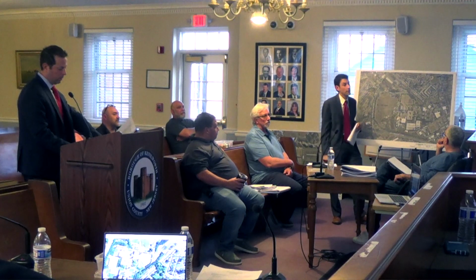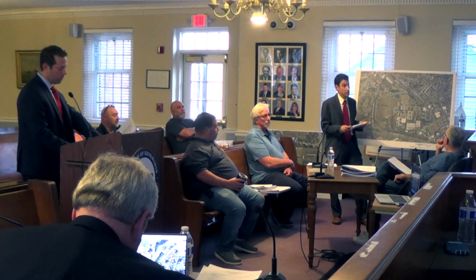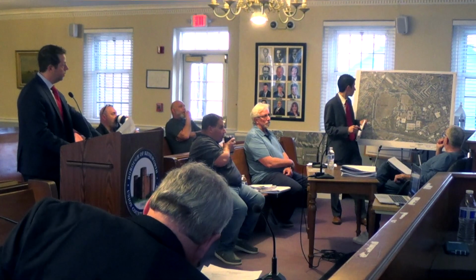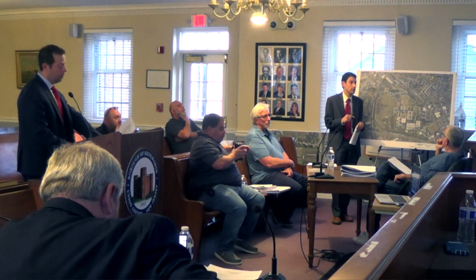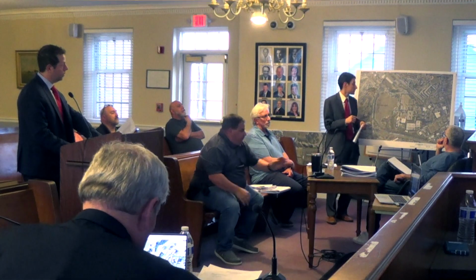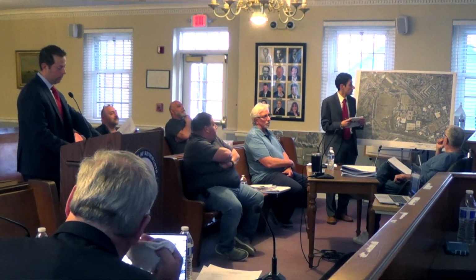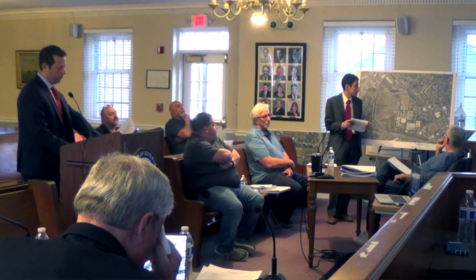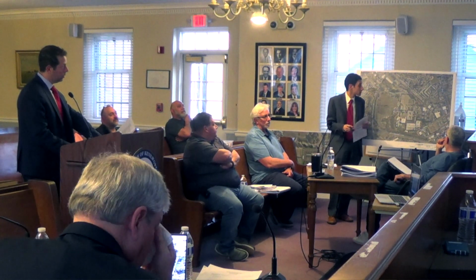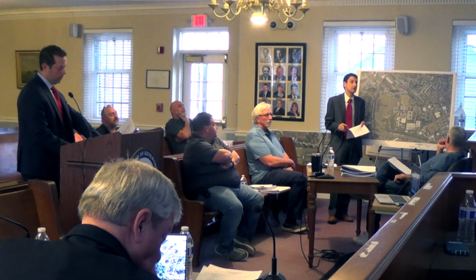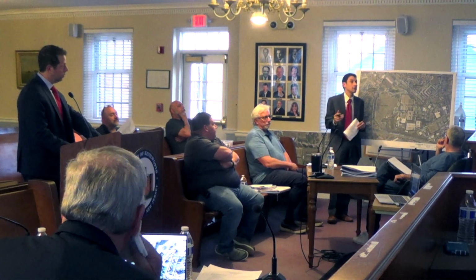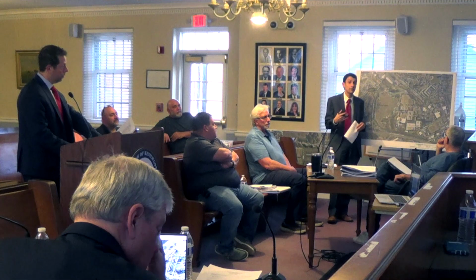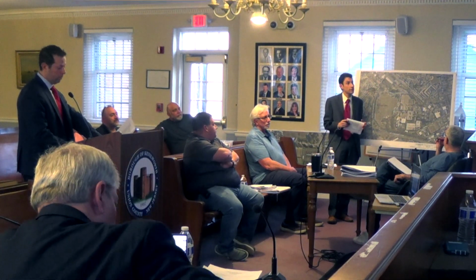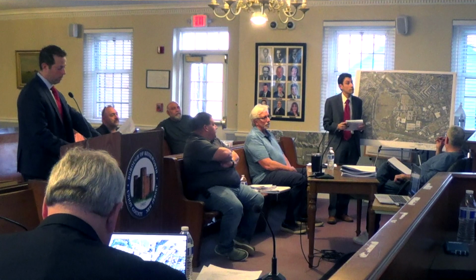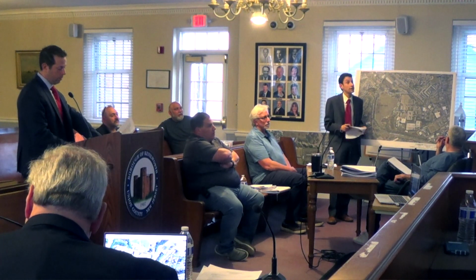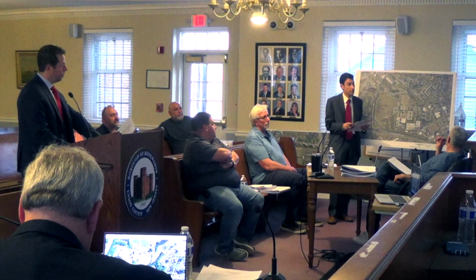The substation will be fed by new PSE&G lines, which we expect will be underground. They are planning on bringing a service underground from Galloping Hill Road on the north side of the site, as well as another service from the south side, coming through either South 31st Street or Swenson Drive. PSE&G has not finalized the final alignment of these feeder lines. We've had 2 meetings with them regarding the alignment, and they are working on finding a corridor now through the site to feed this substation.